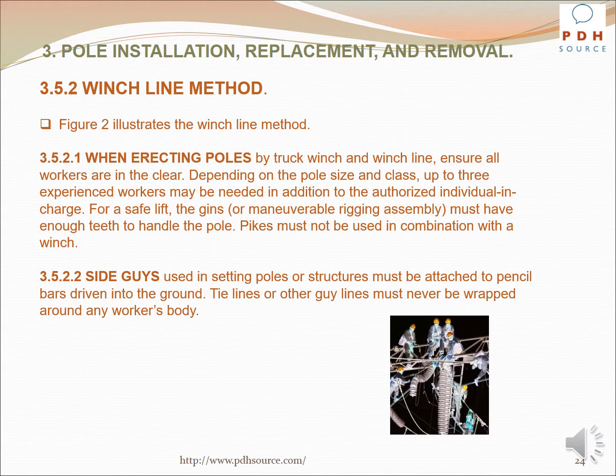Figure 2 illustrates the winch line method. When erecting poles by truck winch and winch line, ensure all workers are in the clear. Depending on the pole size and class, up to 3 experienced workers may be needed in addition to the authorized individual in charge. For a safe lift, the gins or maneuverable rigging assembly must have enough teeth to handle the pole. Pikes must not be used in combination with a winch. Side guys used in setting poles or structures must be attached to pencil bars driven into the ground. Tie lines or other guy lines must never be wrapped around any worker's body.